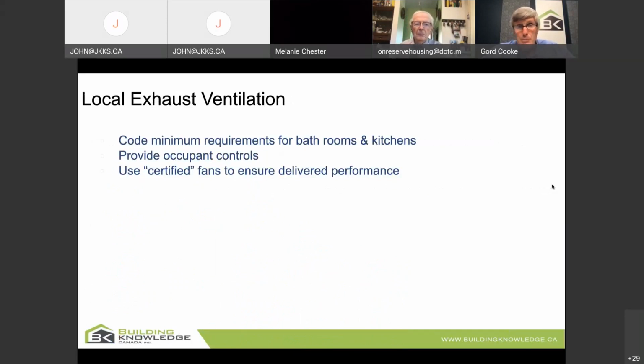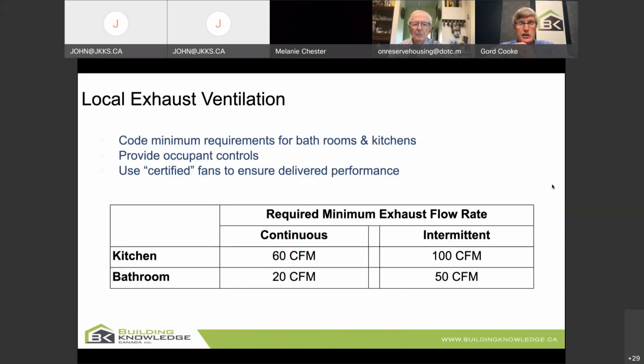So 15 CFM per person is what you need. And then in addition to that, we would say you still need the capacity in bathrooms for either 20 CFM continuously or 50 CFM intermittently. Kitchens, 60 CFM continuous or 100 CFM intermittent. There's a lot of pollutants coming off of stoves, cooking odors and so on, and grease and fats and volatiles. So you really would like to exhaust at the source, either with a continuous exhaust port from there or a separate range hood or bath fan.